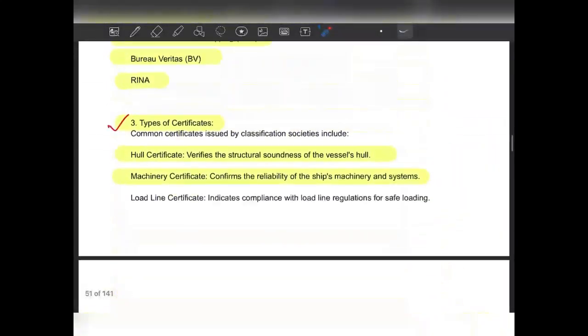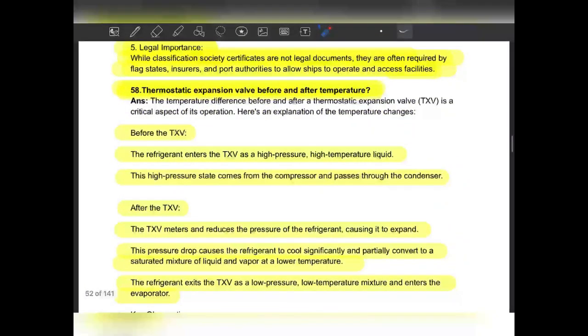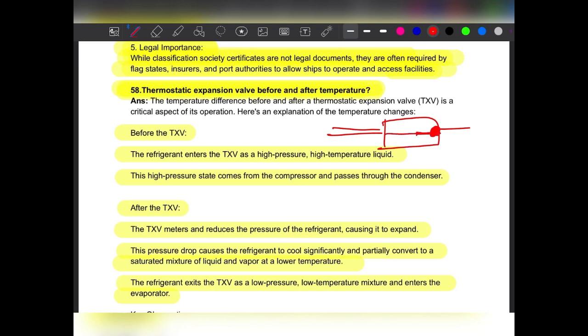This TXV valve, thermostatic expansion valve. I will explain in a very simple way. Thermostatic expansion valve is a type of valve where there is a very small hole and very small nozzle, and when the liquid refrigerant passes through this very small diameter, there will be a pressure drop. Pressure will drop, then temperature will also drop. Pressure is directly proportional to temperature. If pressure drops, temperature will drop. Let's suppose the refrigerant is coming from the compressor at high pressure.